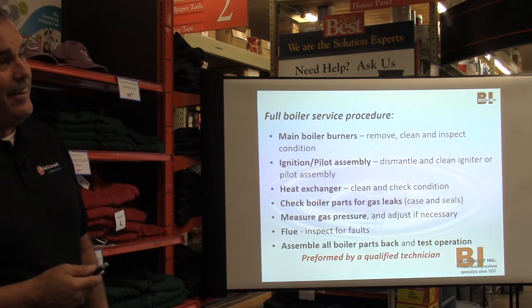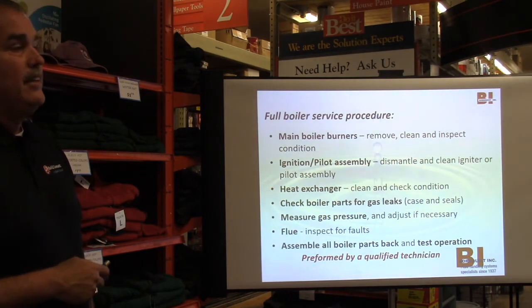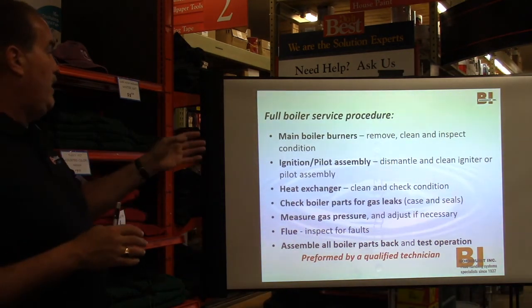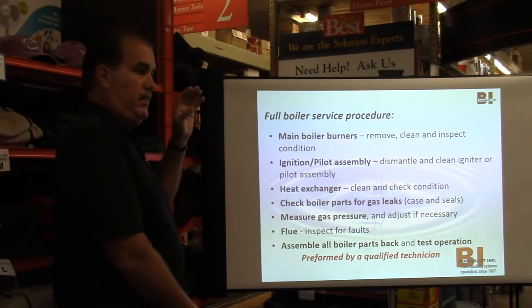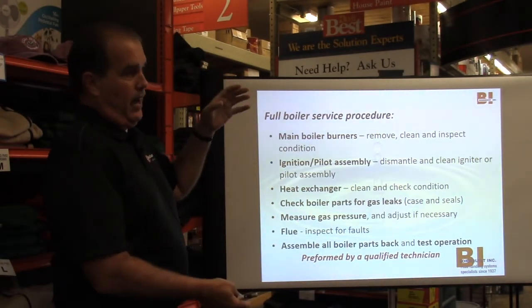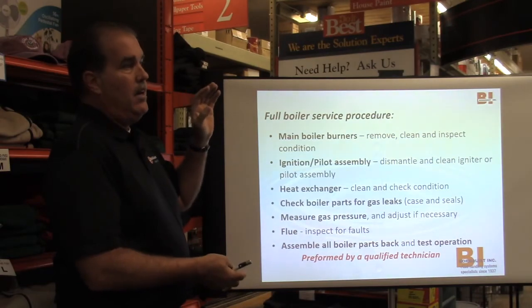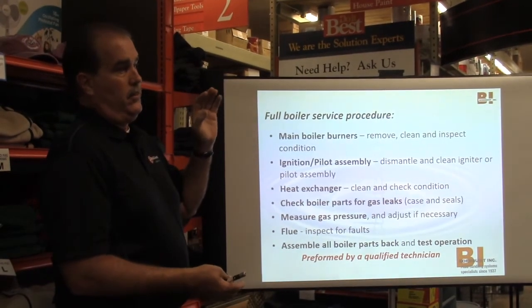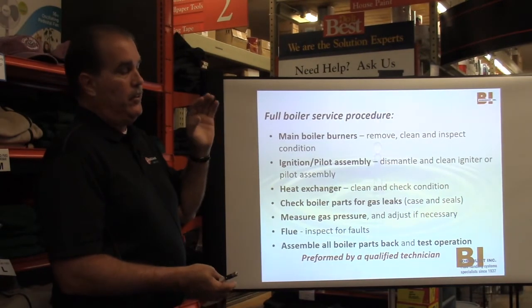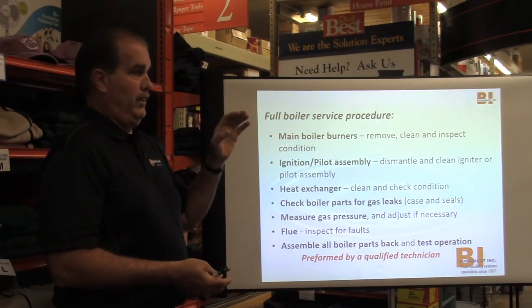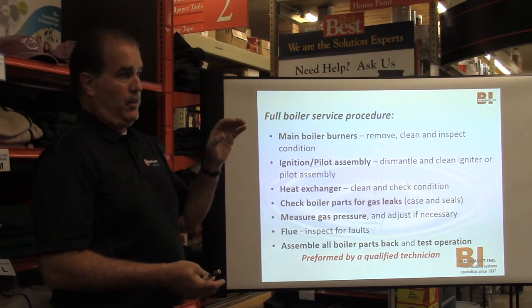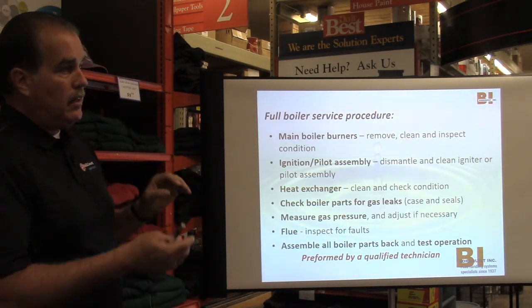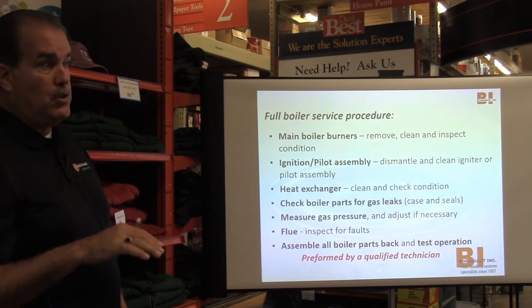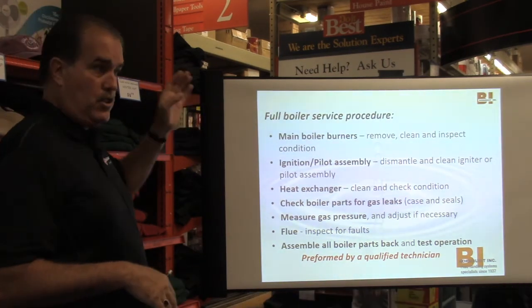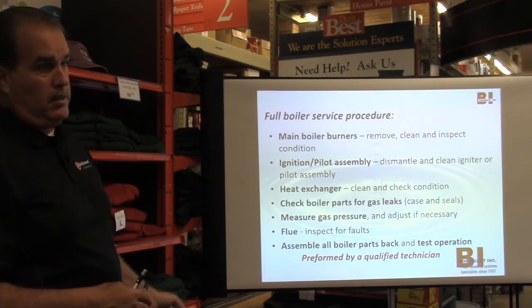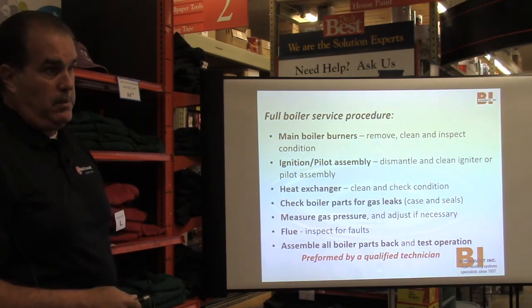Are all these things you're showing us now true for both steam and hot water systems? Yes. But bear in mind, I blend everybody. So this is probably the absolute Cadillac of maintenance. Your manual, if you still have it for your piece of equipment, and if you don't, Google it, because you can get the manual for your particular equipment right off the internet. It'll lay out exactly what they want you to do, and that's what you should be following. I'm just saying, as a general rule of thumb, these are some of the things that I feel are important that they should be checking for.